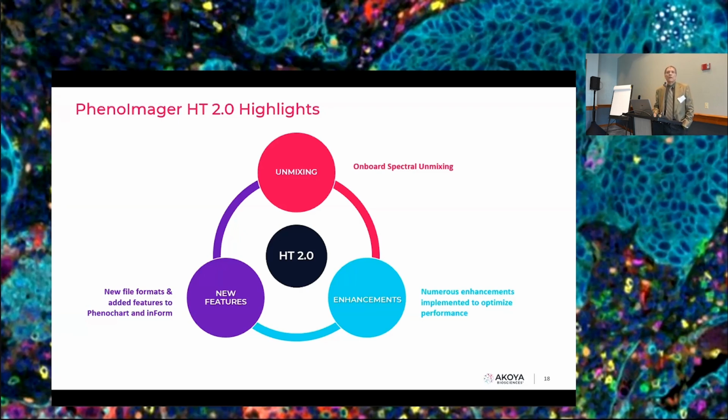And so what we did was we wound up providing for a 16-bit format so that when the samples were unexpectedly bright, they were not saturated. We could still recover them with full accuracy. And that's at a technical level. What it tells me at an operation level and what people are doing is, I don't want to have to scan a slide twice if this one turned out to be unexpectedly bright. Operational factors like putting them all in and knowing that when you scan them once, they're all done and I didn't have to go back and revise or adjust anything. Those are becoming important because of the kind of work that it's being put to.